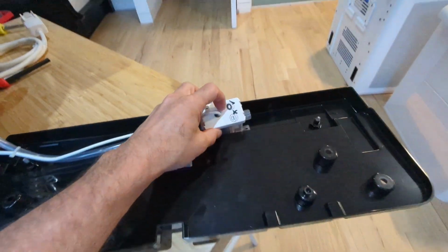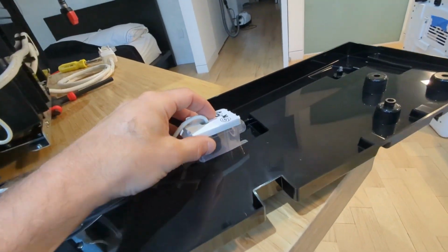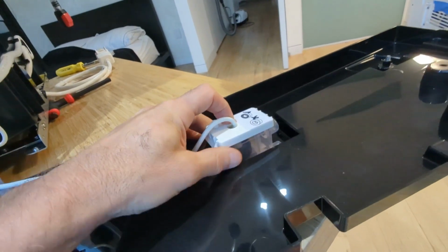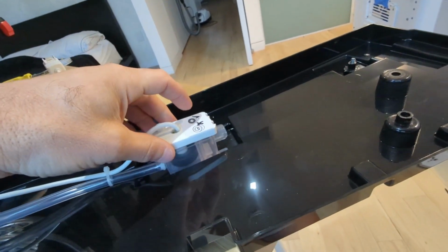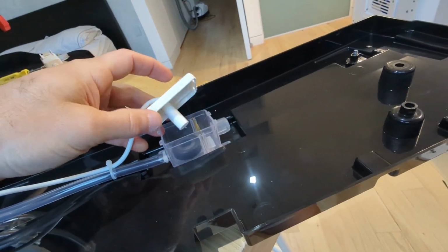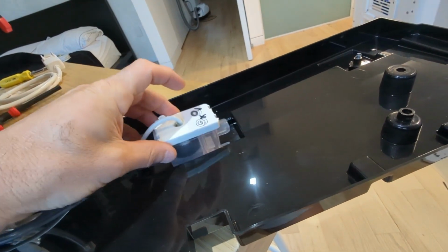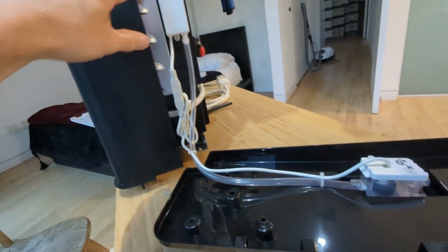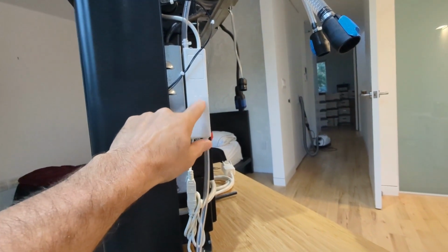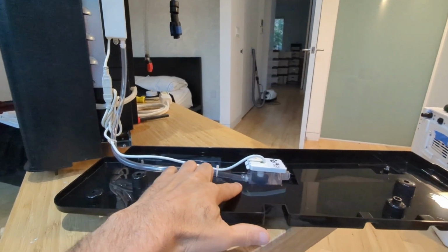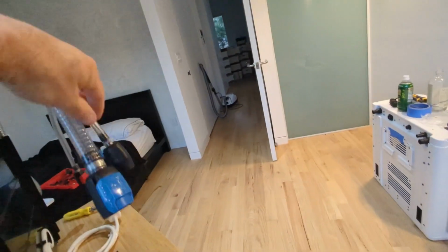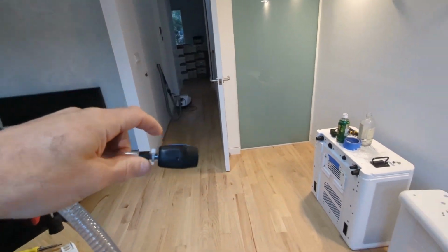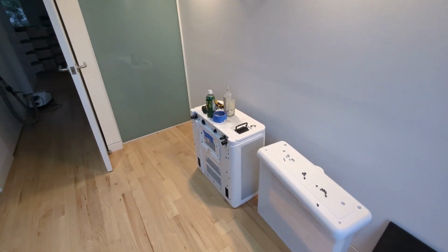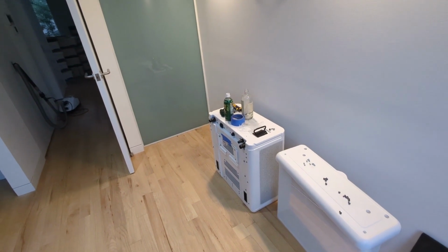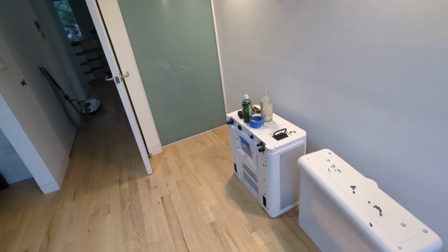And at the bottom of that pan, you have this little reservoir receptacle that the water is going to flow into. And as it fills up, that little magnet's going to float and trip this switch here. And that switch goes up here to the condensate pump, which is going to turn on and pump most of the water out of this pan, up through here and then out through that condensate connector, where it's going to go to the outdoor unit and drip over the condenser coil, as we saw before, which is going to cool it off and make it evaporate and go away.